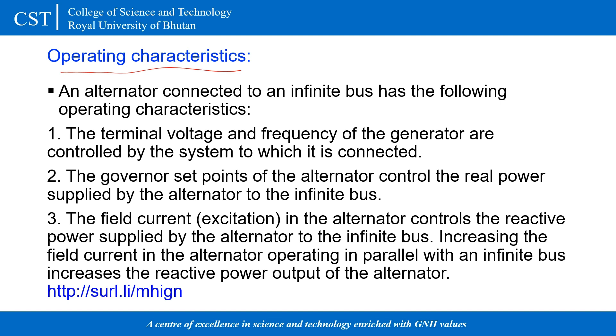The terminal voltage and frequency of this generator are controlled by the system itself — they remain constant even with removal of load, removal of any generator, or addition of a generator. The governor set point controls the speed of the alternator, which controls the real power. The field current in the alternator controls the reactive power — increasing or decreasing the excitation current will increase or decrease the reactive power accordingly.